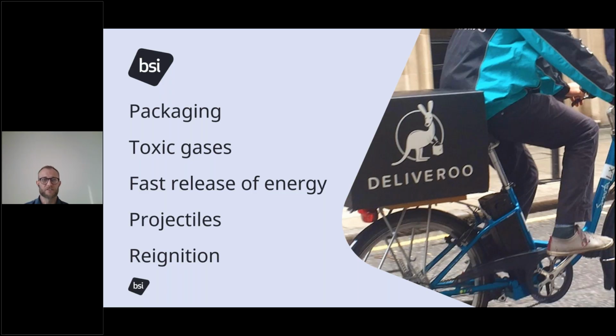The challenges are similar for electrical items with batteries up to this size. Consider what happens if you drop a battery-powered tool. Mechanical damage to the cell could compromise the internals and create a short circuit. It only takes one cell to have an issue for it to develop into a full-scale failure of the battery pack. Failure might not be immediate, it's often delayed, so it's probably best not to put that dropped tool back with the other spare batteries in the work van.